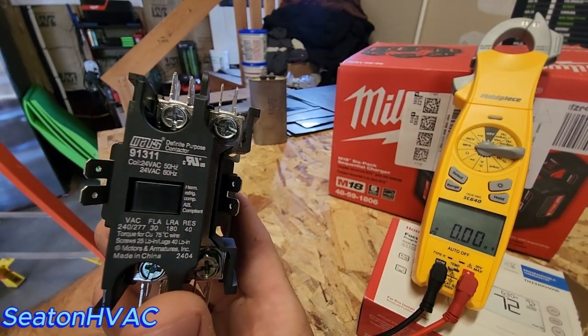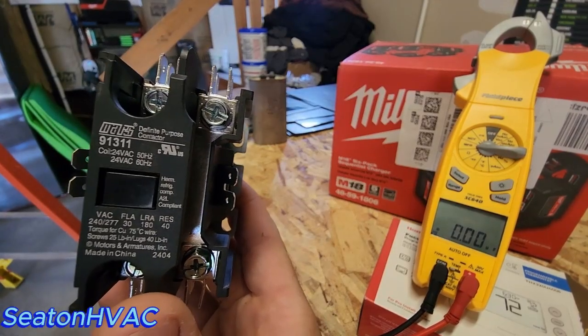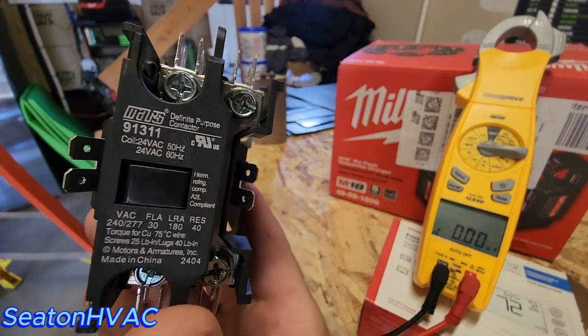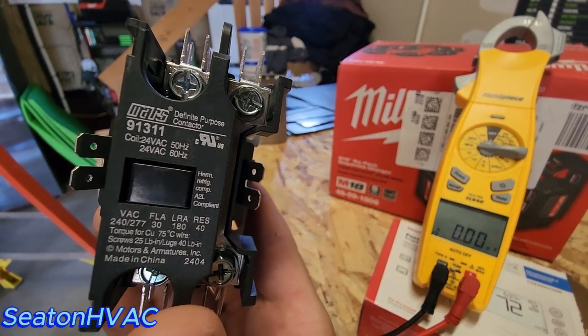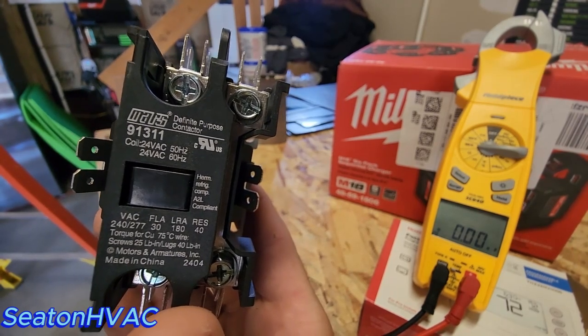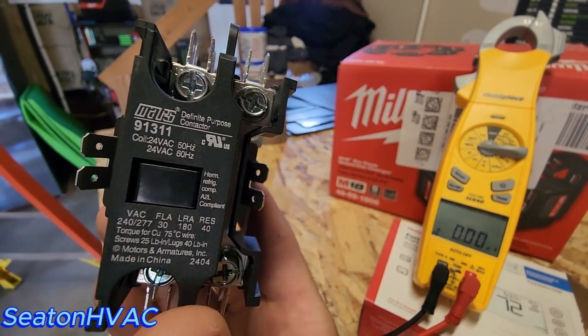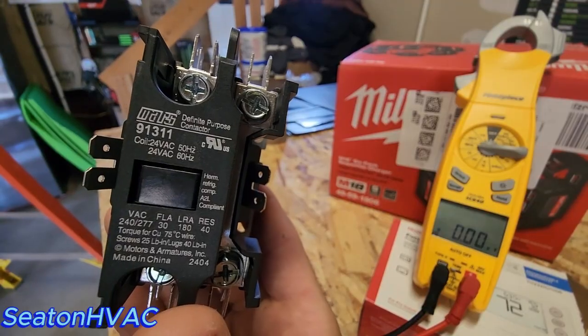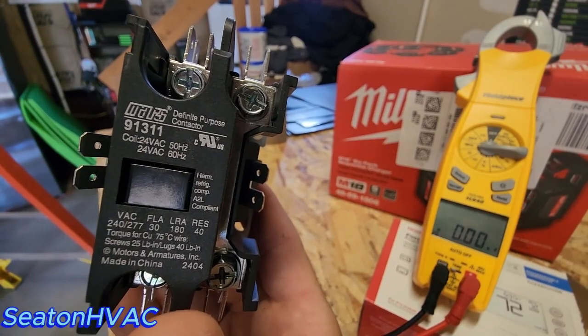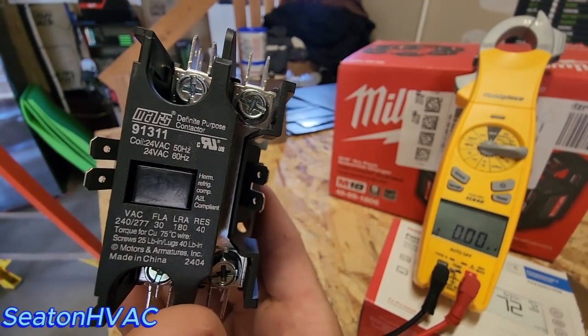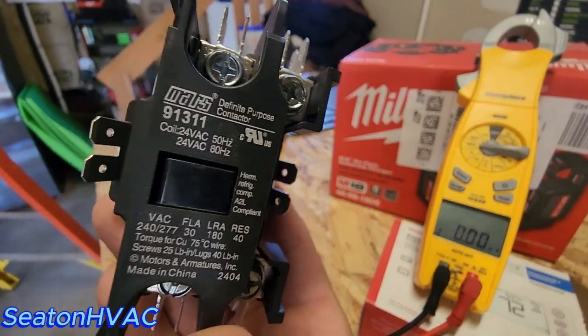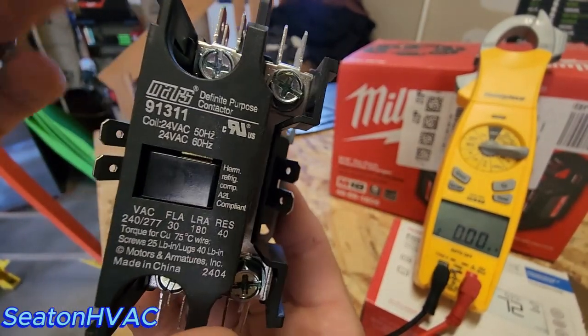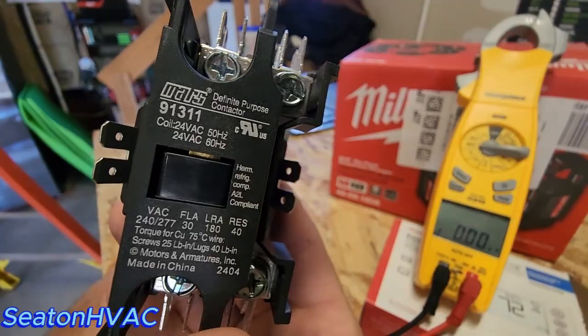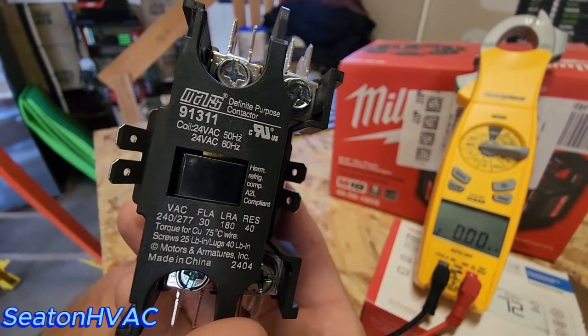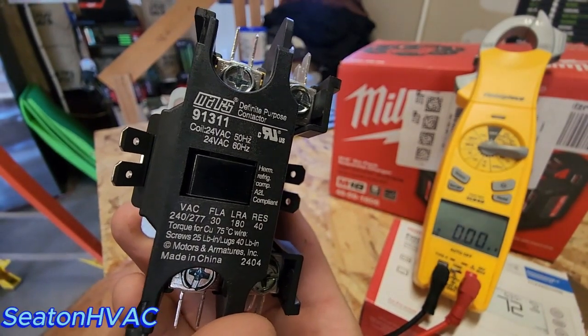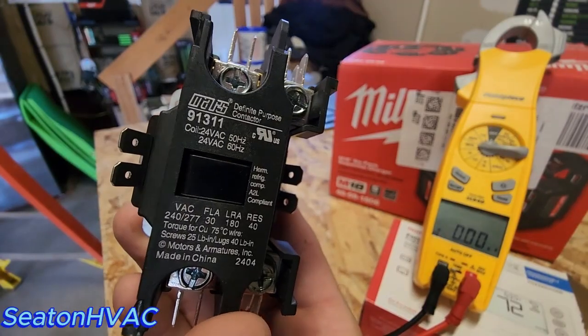So what general rule of thumb for me, it's almost like a good superheat reading on an air conditioner. I think between 8 and 18 ohms works well. It's a good rule of thumb. Anything out of that range, usually if you have a dead coil, it's going to give you a real low number, and you know it's bad, and the equipment's not working, so it's pretty obvious. So let me show you how we do that real quick, and then we'll move on to the next thing. It's going to be a long video today, I think.